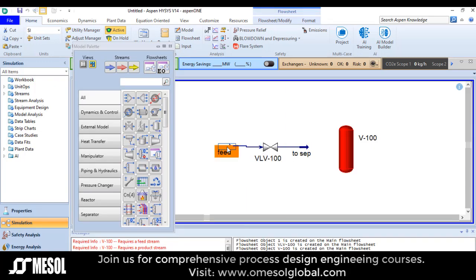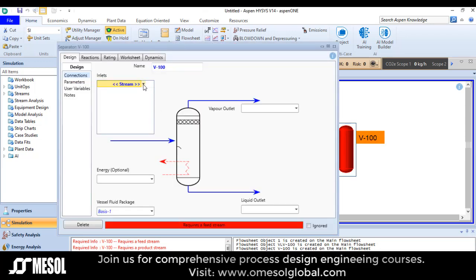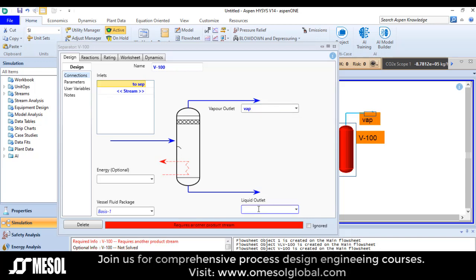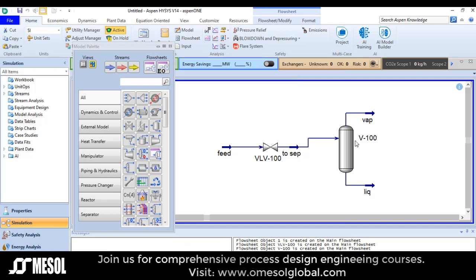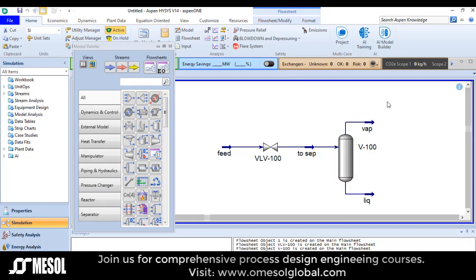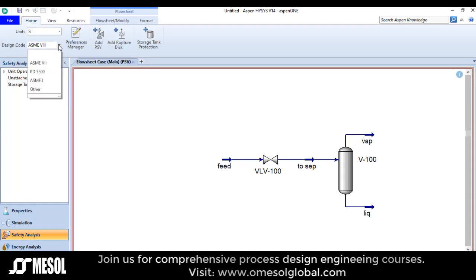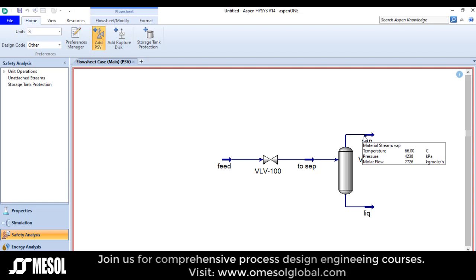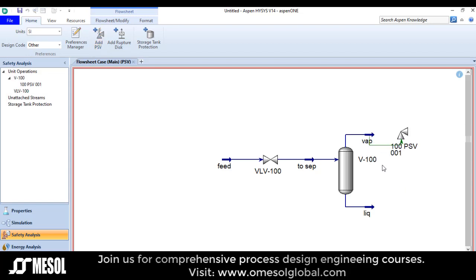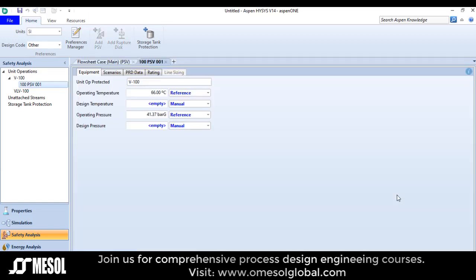Now double click the separator. This is my vapor out and this is the bottom. In order to put a PSV on the vapor stream, you can click on the pressure relief option or go to safety analysis. If you are using API code, it is better to use 'other' and then click on the add PSV button, go near the vapor outlet and click here to place the PSV.